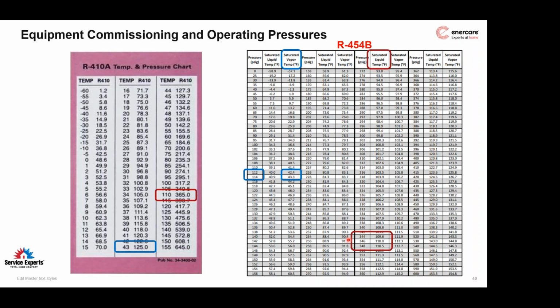Oh, sorry. Go ahead, Richard. No, sorry to interrupt you. I didn't mean to do that, but I do have a question. Yeah, sure. Shoot. As far as we're concerned, though, we're using new gauges that have the temperature and the pressure. We don't use PT charts, so we're good, right? It should be listed as per normal. Yeah, we're not using a different gauge for this gas, is what I'm saying. We're using the proper one. That's correct. As long as it's listed on your gauge, it should be fine. Yep. Okay, cool.